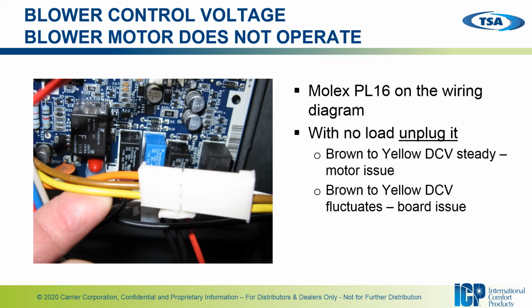So to further troubleshoot, you want to disconnect that harness right there at that junction. You want to disconnect that with no load, so make sure there's no call for blower operation when disconnecting that. Then take your meter and measure between the brown and yellow for your DC volt reading. If your DC volt reading is steady, you have an issue with the motor. If your DC volt reading is fluctuating, that means the issue lies in the control board.